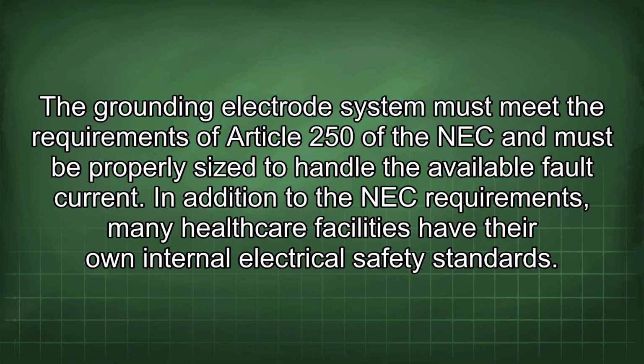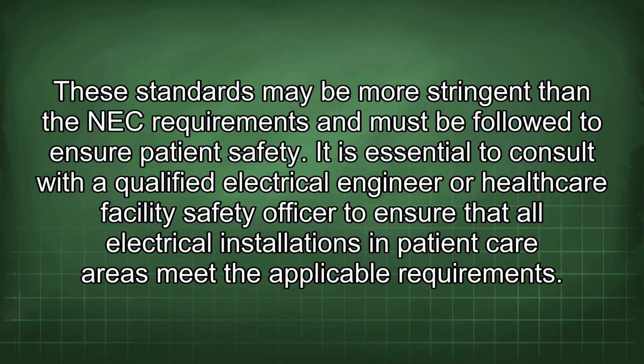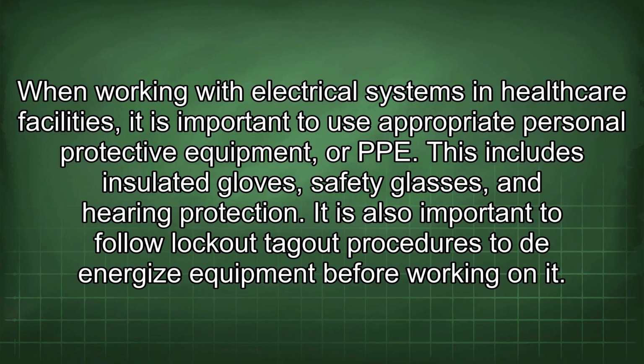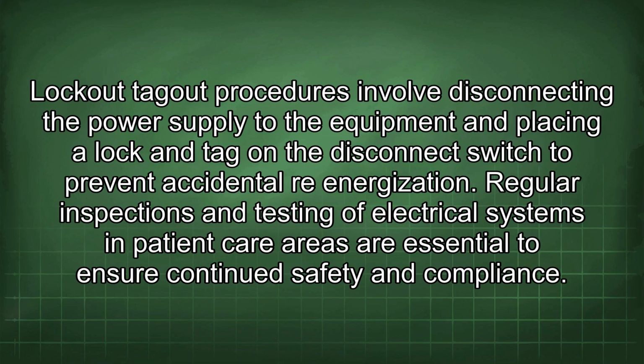In addition to the NEC requirements, many healthcare facilities have their own internal electrical safety standards. These standards may be more stringent than the NEC requirements and must be followed to ensure patient safety. It is essential to consult with a qualified electrical engineer or healthcare facility safety officer to ensure that all electrical installations in patient care areas meet the applicable requirements. When working with electrical systems in healthcare facilities, it is important to use appropriate personal protective equipment, or PPE. This includes insulated gloves, safety glasses, and hearing protection. It is also important to follow lockout-tagout procedures to de-energize equipment before working on it. Lockout-tagout procedures involve disconnecting the power supply to the equipment and placing a lock and tag on the disconnect switch to prevent accidental re-energization.